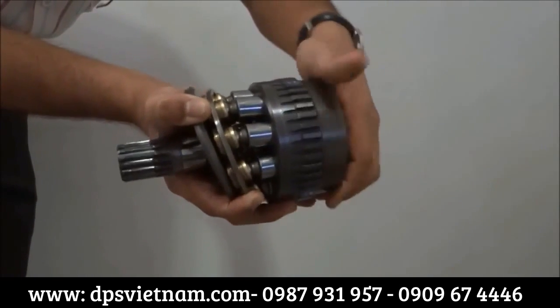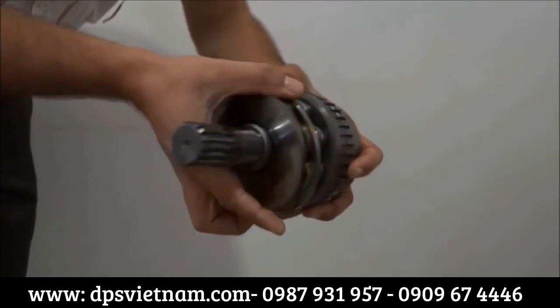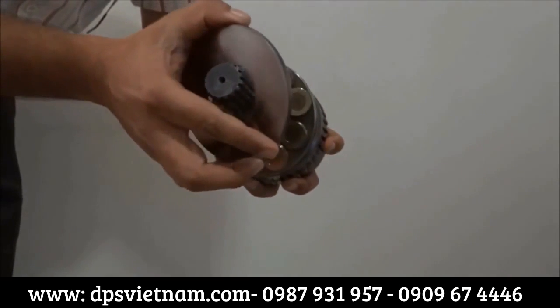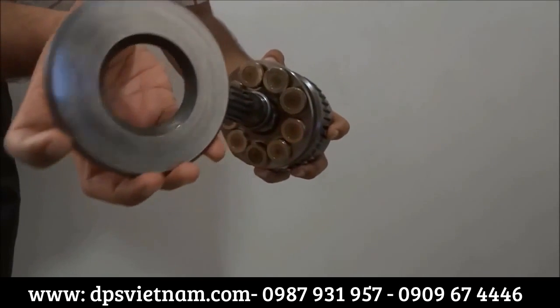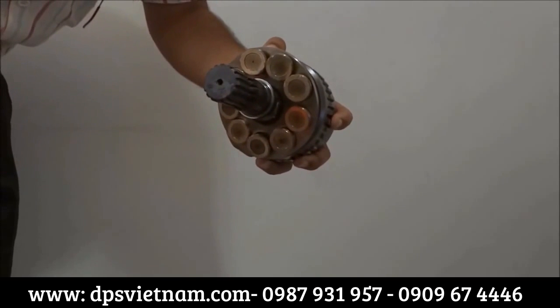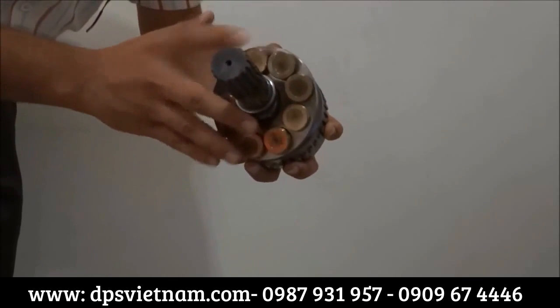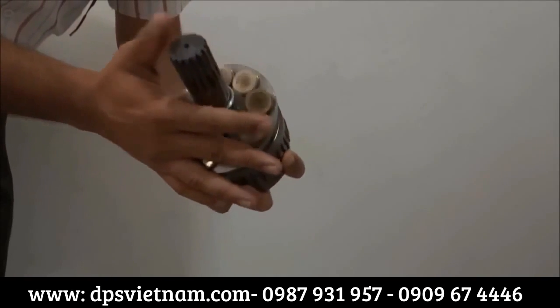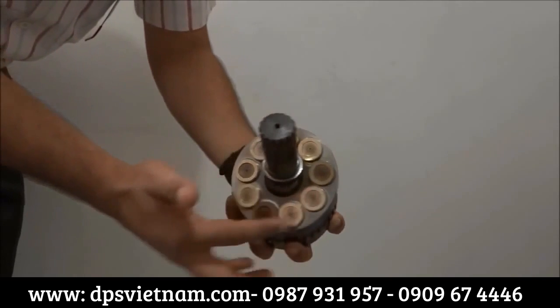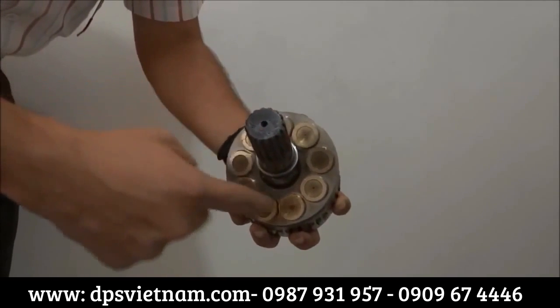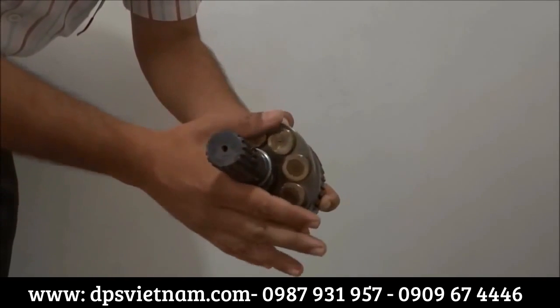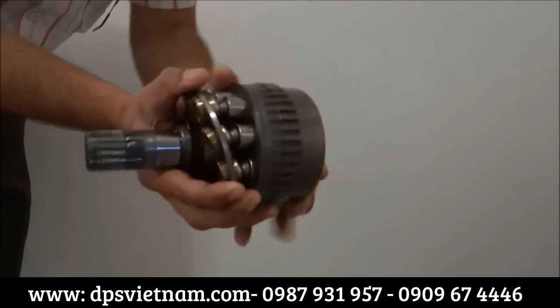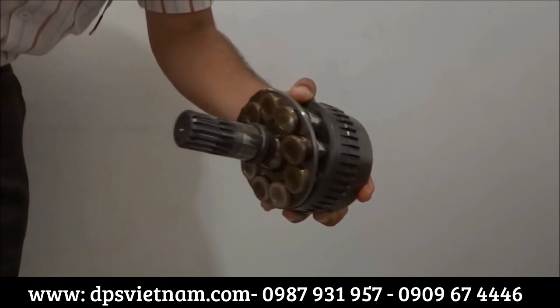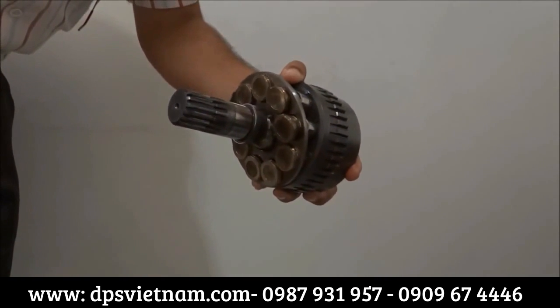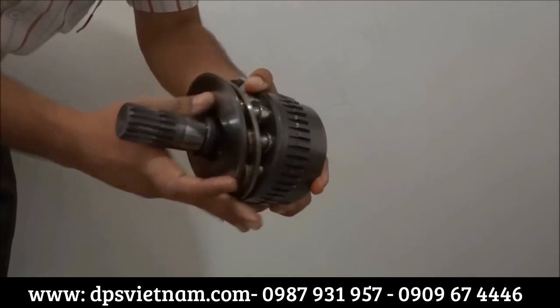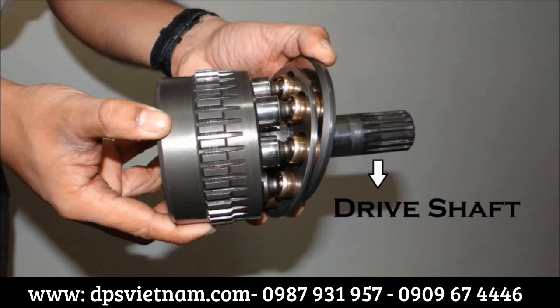So when the swash plate is vertical, there is no flow, and as the swash plate angle changes, the flow varies depending upon the angle of the swash plate, and the swash plate angle is controlled by a valve according to the load and the requirement. So that's the rear side of the piston, which is sliding over the swash plate over there. Okay, now let's have a closer look and identify each component.